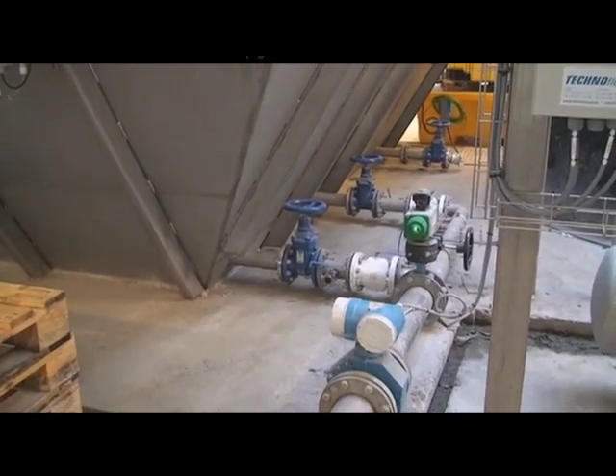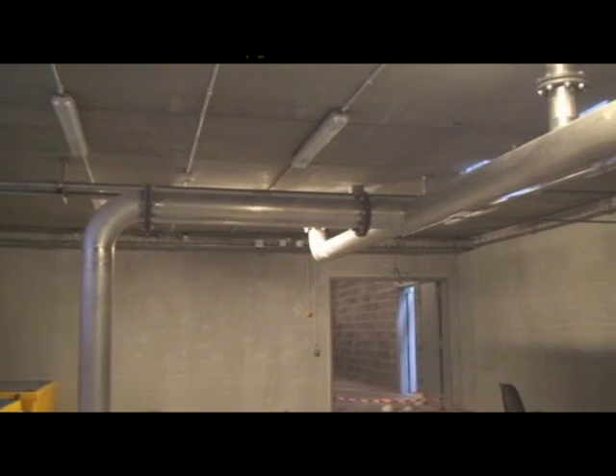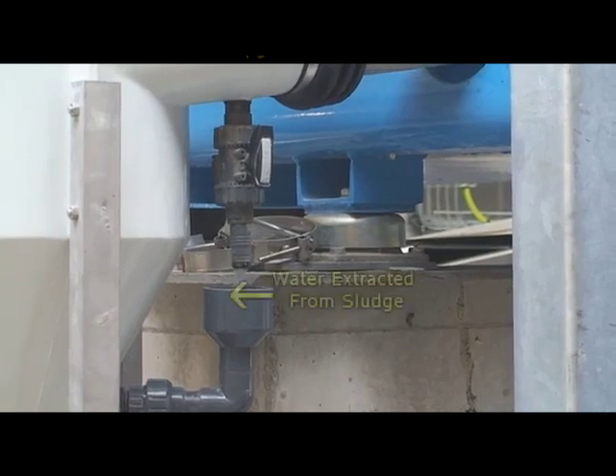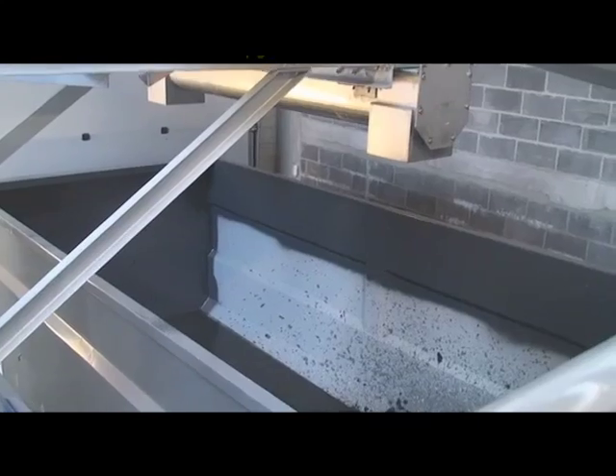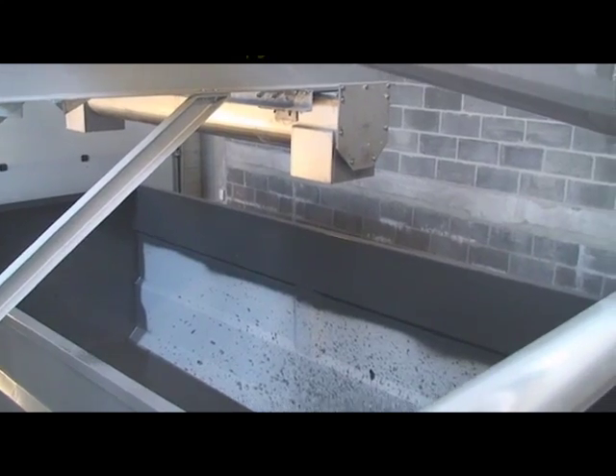Sludge removed from the settling process is emptied to a subgrade sludge chamber. From this chamber, centrifugal pumps move the sludge to a cyclonic separator to remove all the water. Once the sludge is dry, a screw conveyor deposits the material into storage containers for removal. This dried sludge is used for landfill and as a filler component for cement manufacturing.